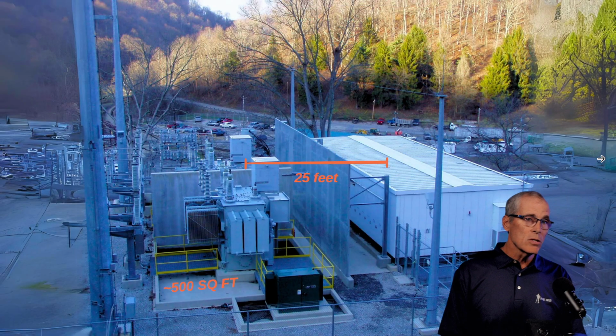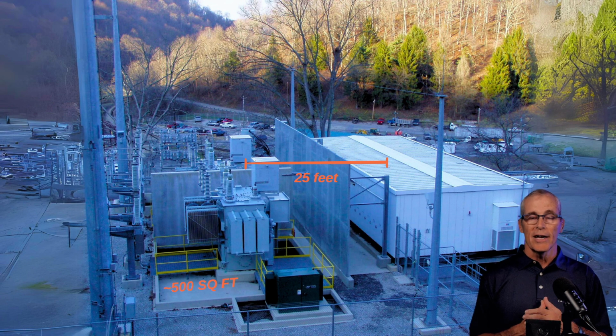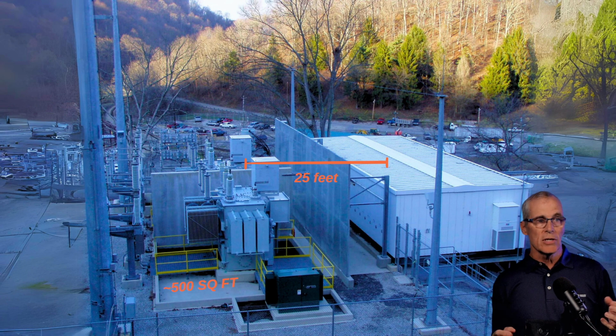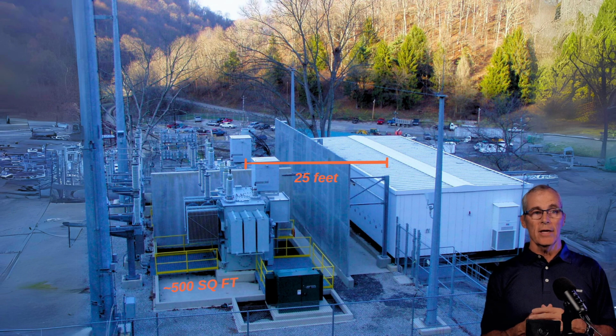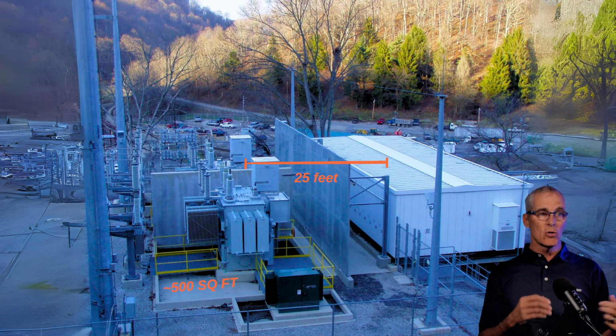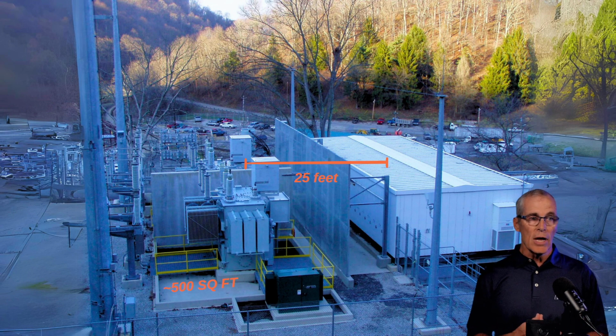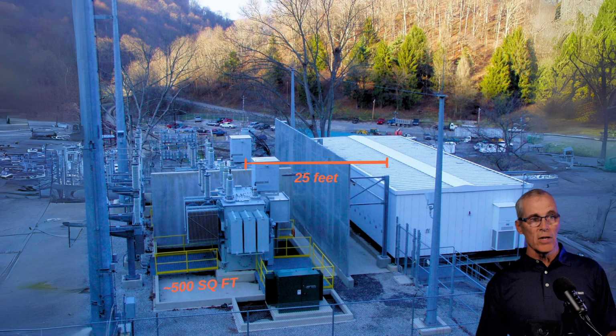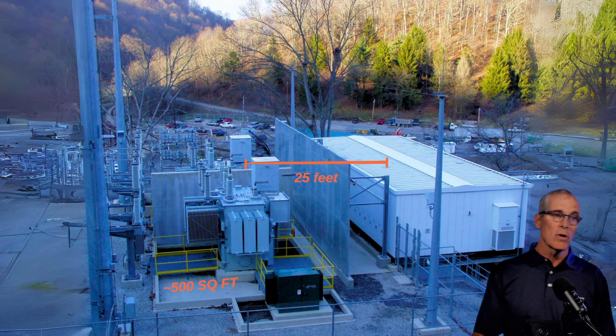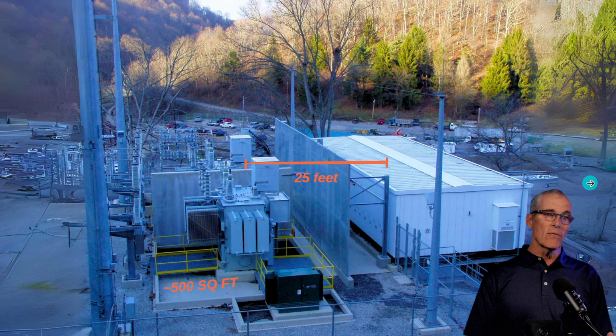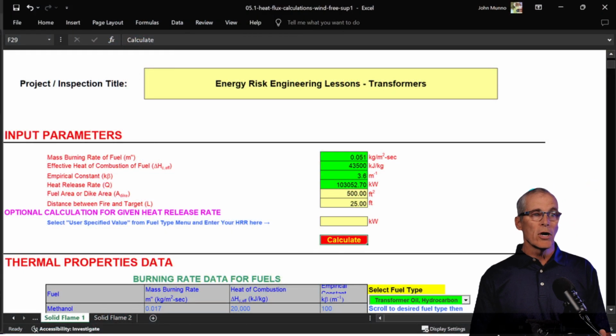Now, for our specific example that we had back at the beginning, what we have here is a gas processing facility with a control building, 2 transformers, and a firewall. We have about 500 square feet of containment for the oil and about 25 feet of separation. If that firewall was not there, we're going to model it, okay?